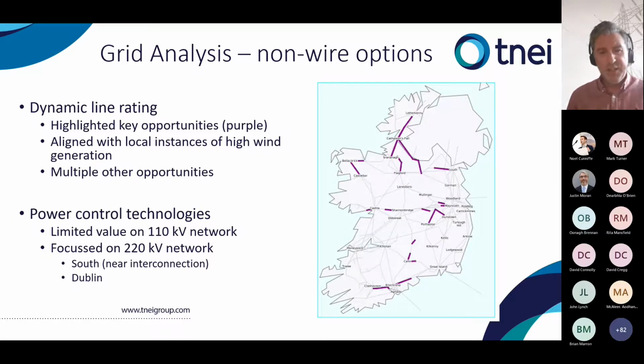Power control technologies, from our assessment, we probably didn't see a huge value on the 110 kV network. So we focused more on the 220 kV network, in particular throughout the south, near where interconnection and conventional and RES interacts. Similarly in the Dublin area as well, where power control is likely to be needed, with large volumes of conventional interconnection and RES interacting in quite a dynamic environment.